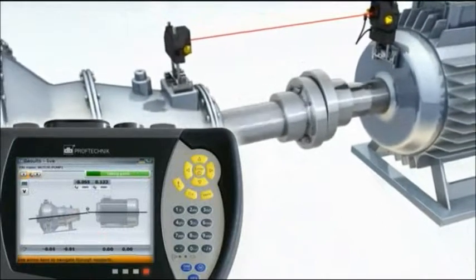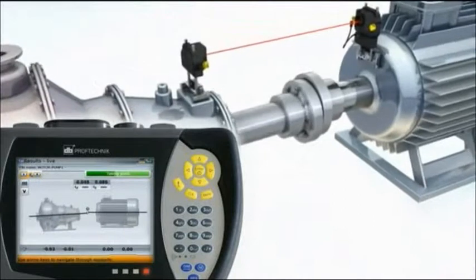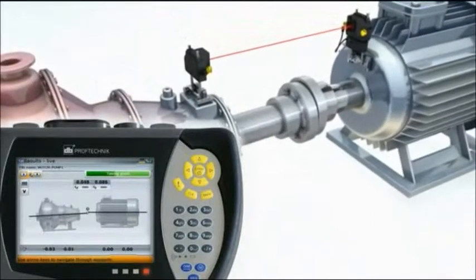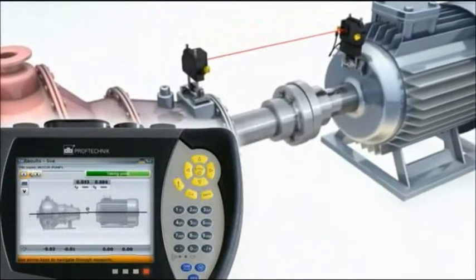Manufacturers' targets often do not reflect the real machine centerline movements due to thermal growth, pipe strain, and other dynamic factors. By applying the measured values, machines are precisely aligned to their true operating conditions.